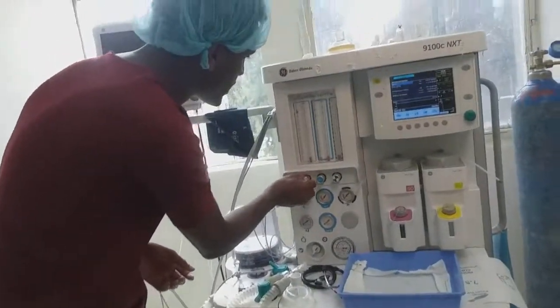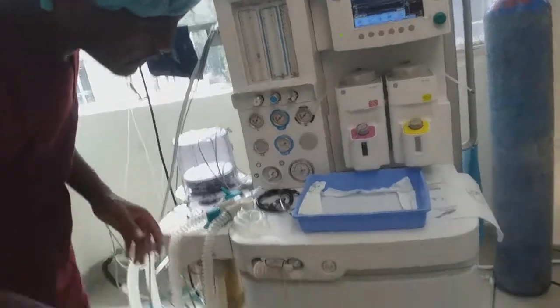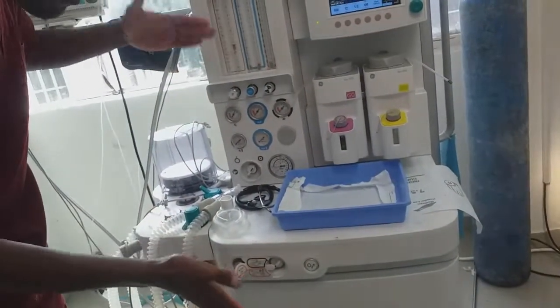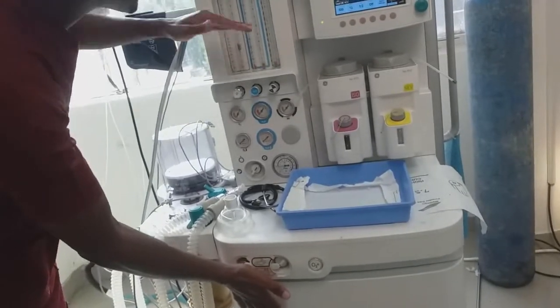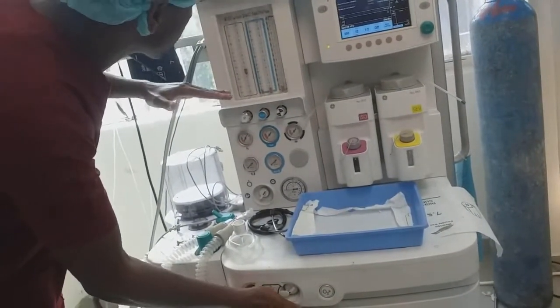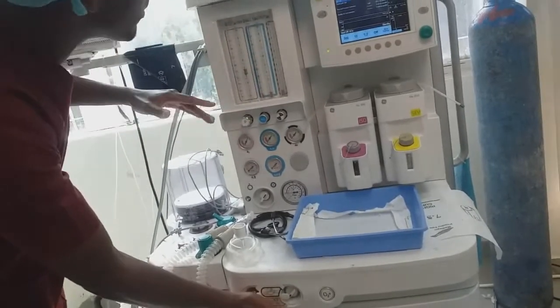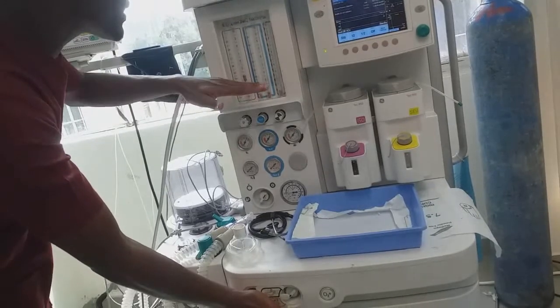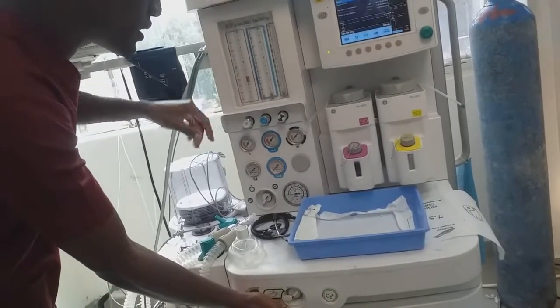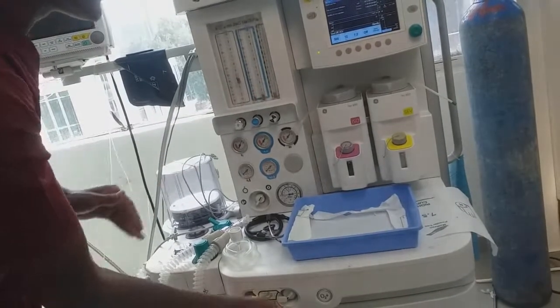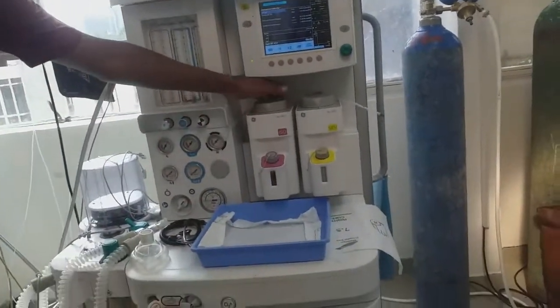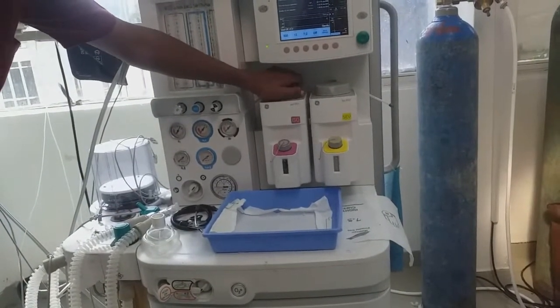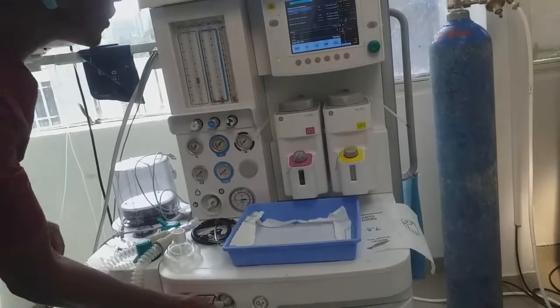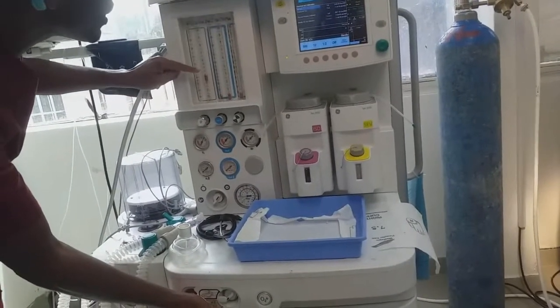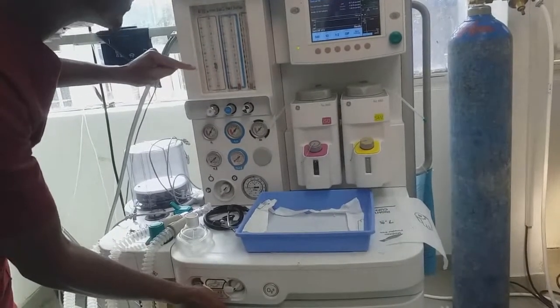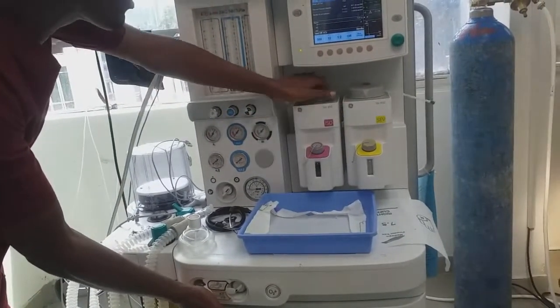Then I open oxygen to some test level. When I check this machine manually, when I press this, it should fall down, fall down. If there is a leak, it just stays stuck here. There is no movement, so there is no leak. We can also check mechanically. The vaporizer is still here. I can also check mechanically. There is minimum movement of the bobbin. This indicates that there is no leak in this vaporizer.